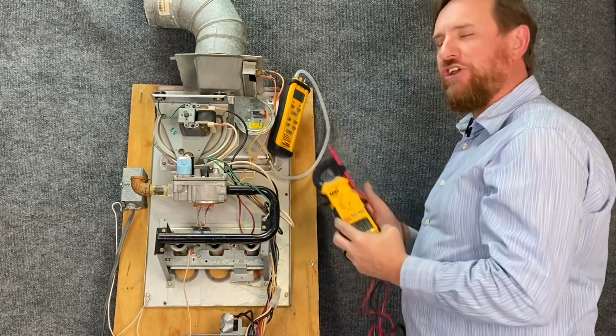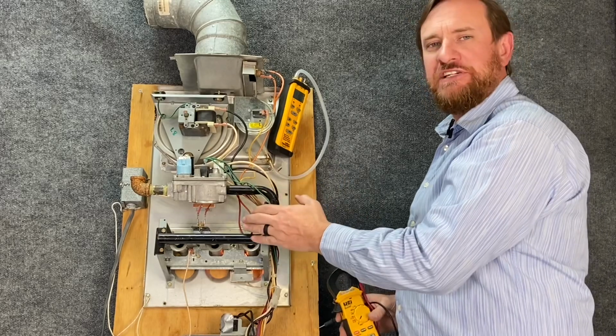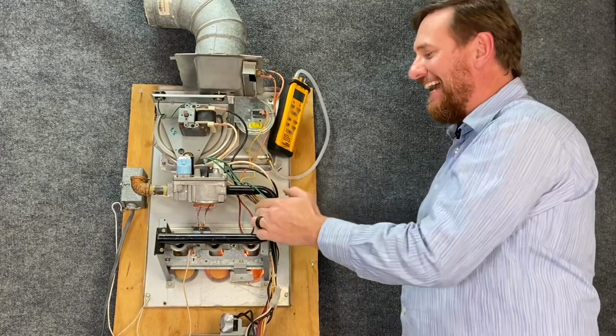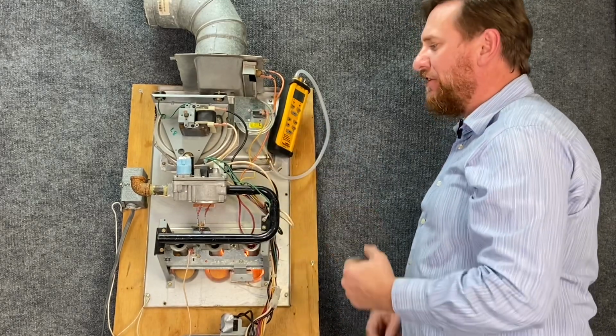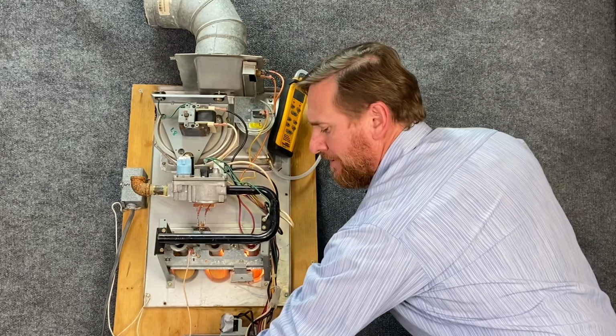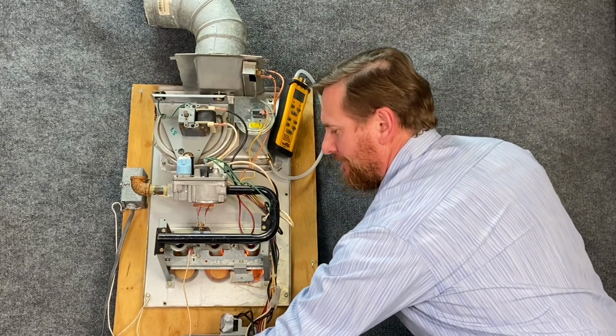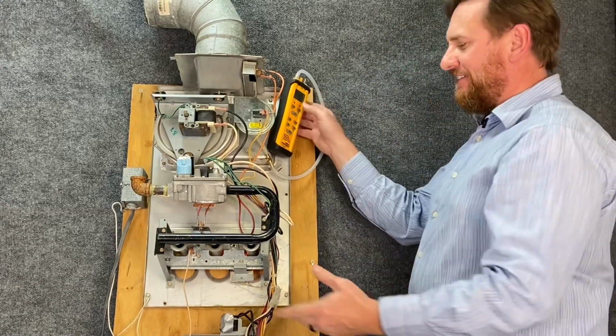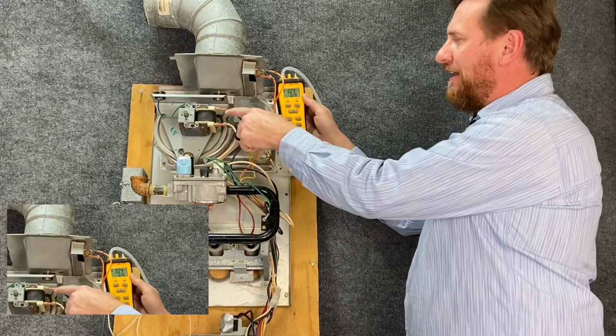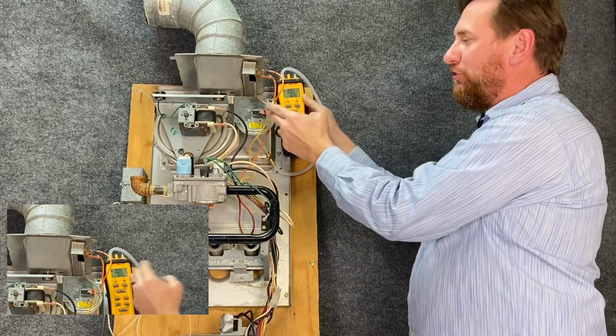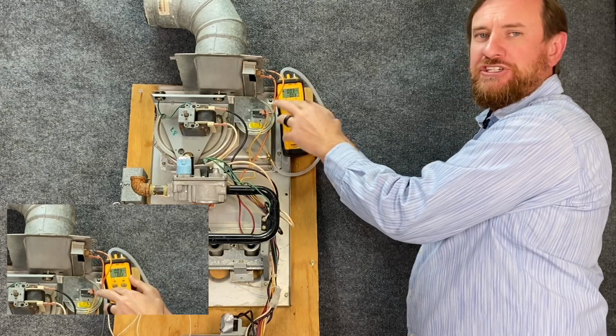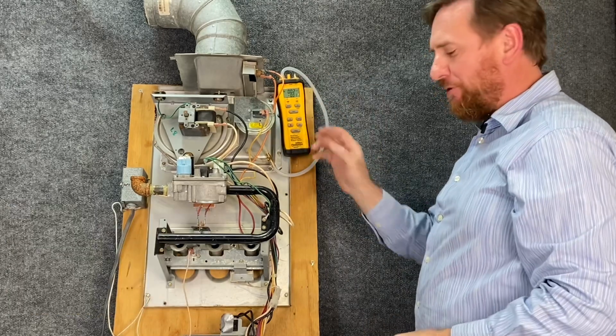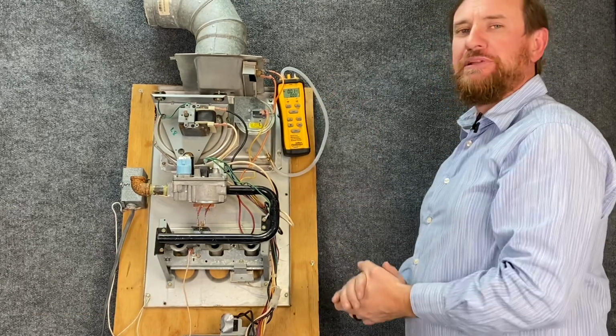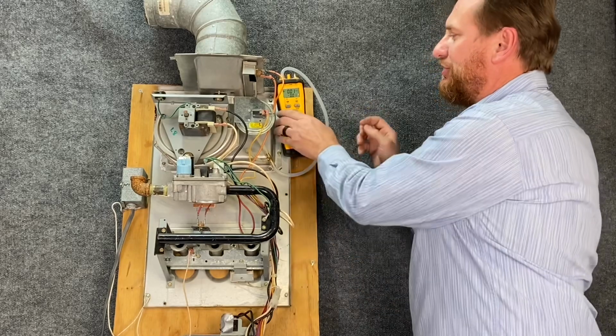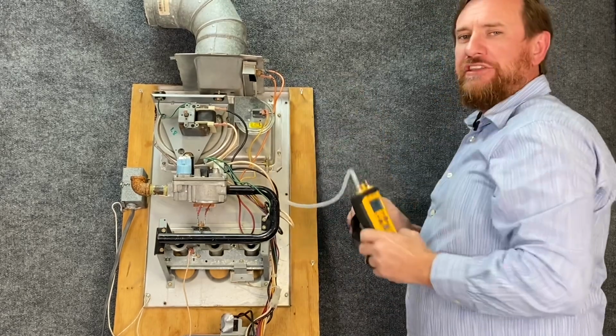So the switch is now closed, and down below our hot surface igniter is getting hot. So we know that that can't happen until the switch closes. So that's a good sign. As I cycle the system off, my inducer fan motor cycles down and I start losing my vacuum. The switch then goes back to its open position. The control board knows that it should be open. Everything is working correctly, as it should. That's one way to check the switch.